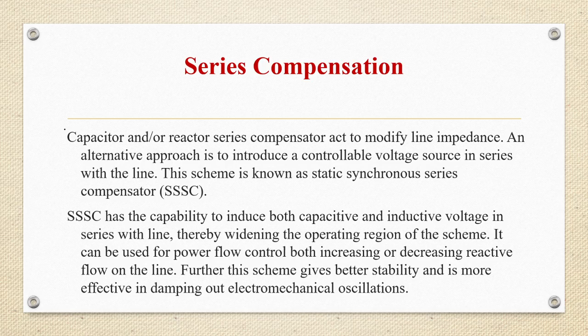So the static synchronous series compensator has the capability to induce both capacitive and inductive voltage in series with the line. It will be used for power flow control, both increasing or decreasing reactive flow on the line. This scheme will give better stability and is more effective in damping out electromechanical oscillations.